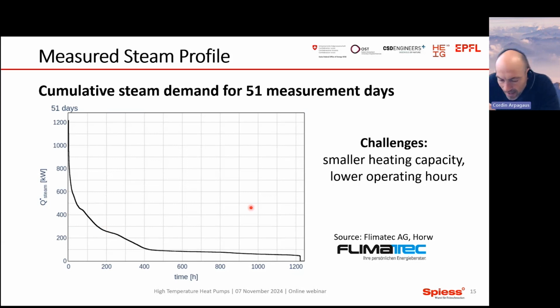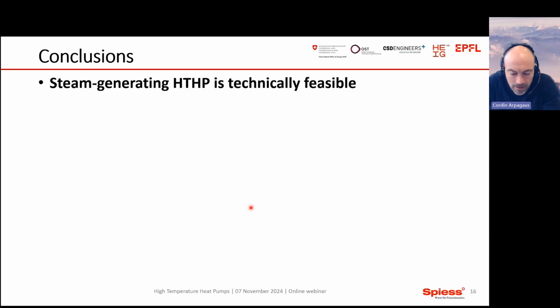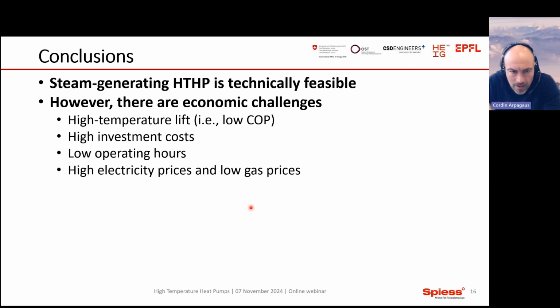This whole further analysis and monitoring of the real steam profile is very, very important to make decisions. We can conclude at that status of the project that a steam generating heat pump is technically feasible, but we have economic challenges: quite high temperature lift, low COP, high investment costs compared to other technologies. We also recognize quite low operating hours, and very much fluctuation of the steam demand for these sausage and meat cooking cabinets. And the electricity prices are higher again, and the gas prices are lower again. So all of these four parameters are not so much in favor of the heat pump.